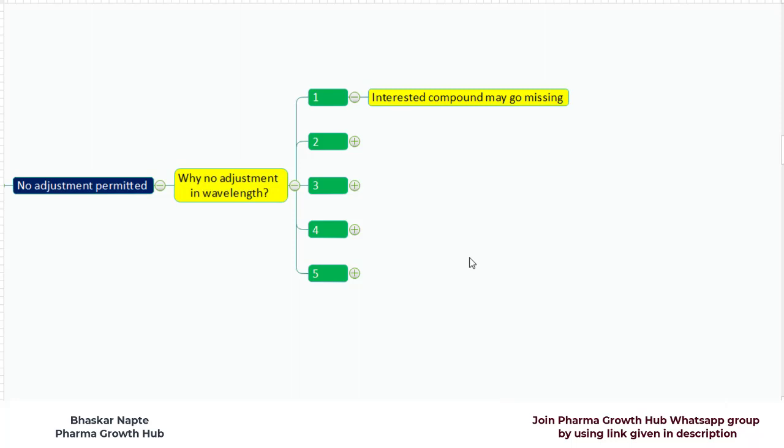You will not be able to detect that impurity and hence you will not be able to understand the content of that impurity in your sample. This is a very dangerous situation, and because of that the change in wavelength is not permitted.